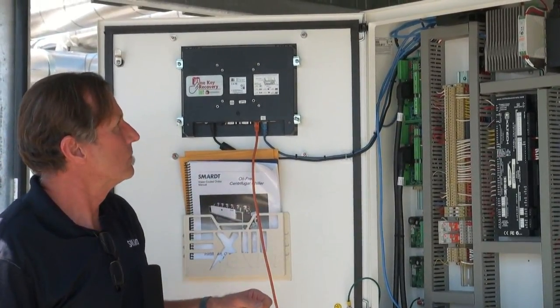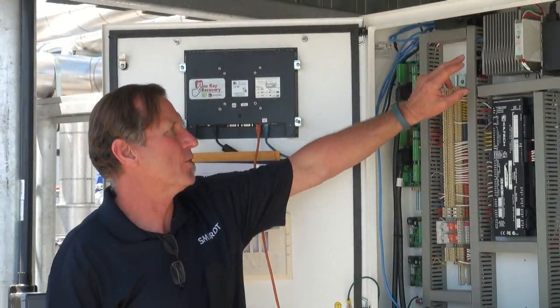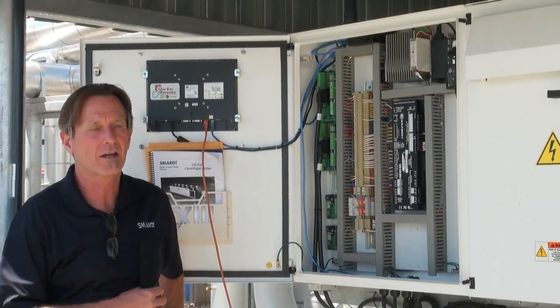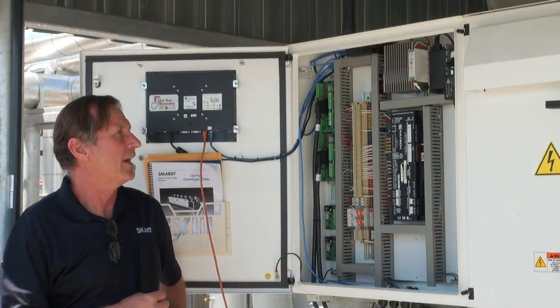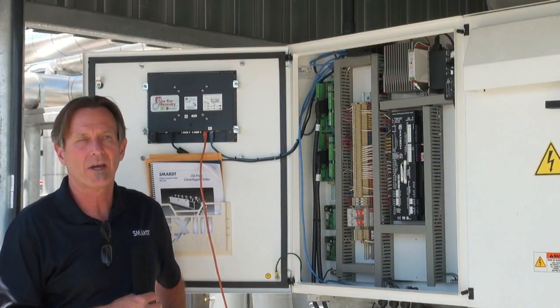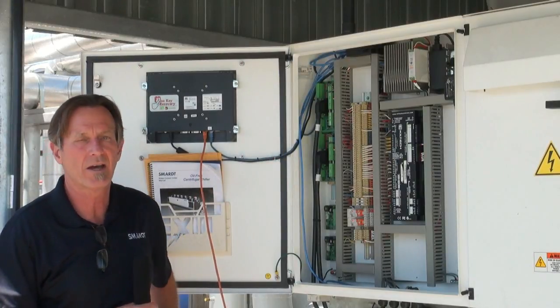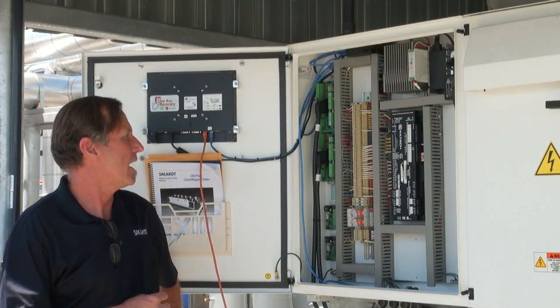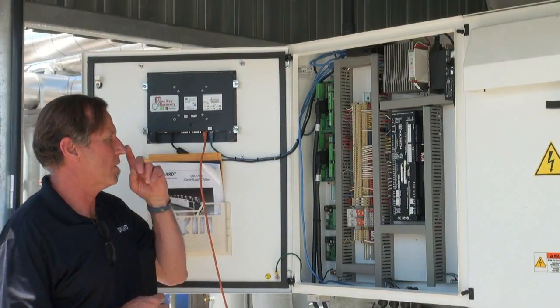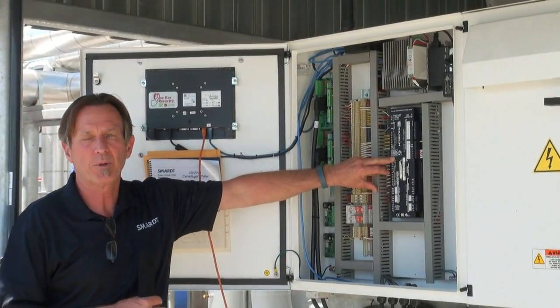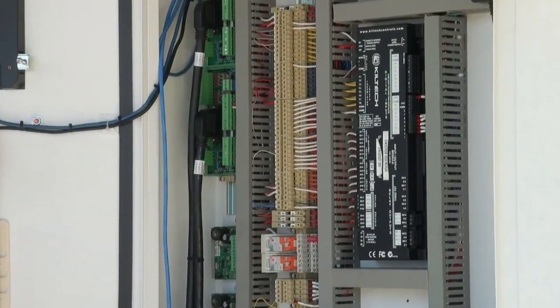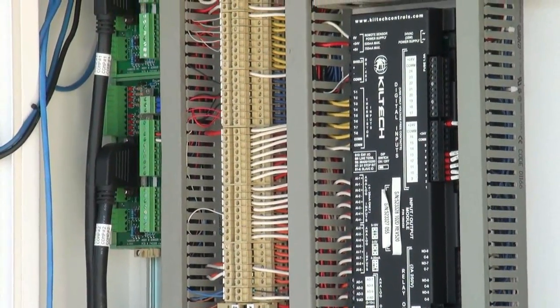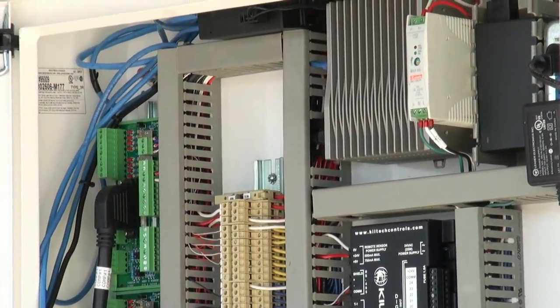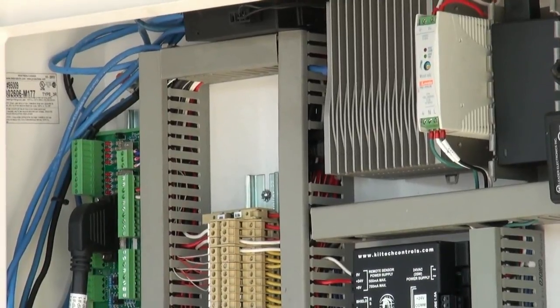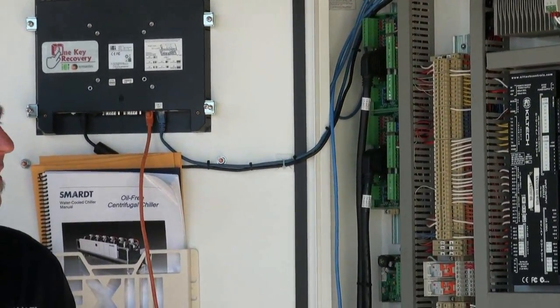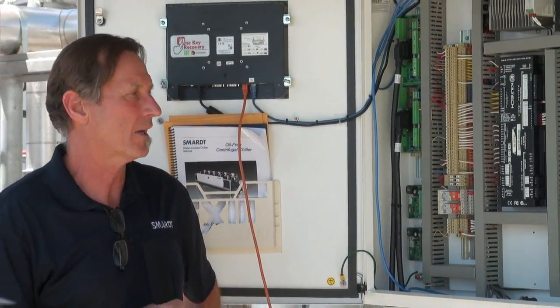The main controller for the chiller is this box up here. That has all the logic for the controller for the chiller, and it's in communication with the entire chiller. So it's in communication with each compressor through the Modbus link. Also, this is the I/O board, the input-output board for the controller. So it's basically the arms, feet and hands of the controller. It has the analog inputs and outputs, and digital inputs and outputs. That's the actual board, and it's in communication with the controller as well. So it's all done through a 485 Modbus link.